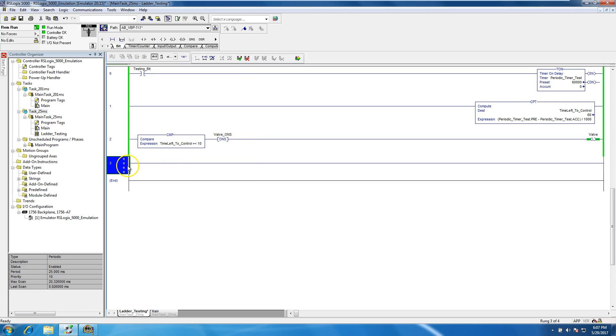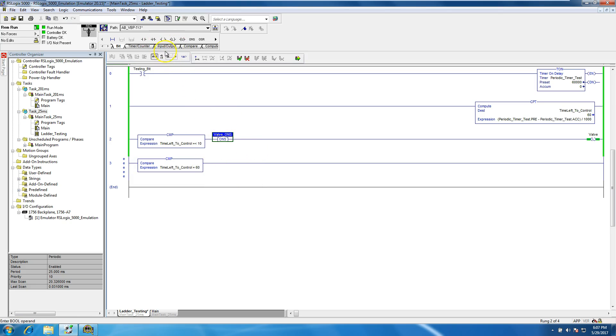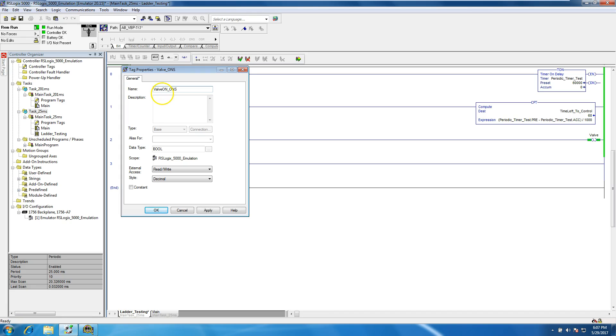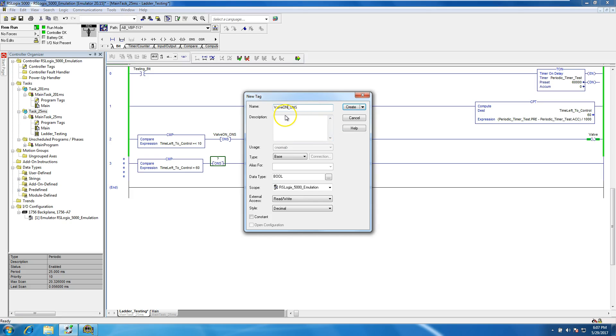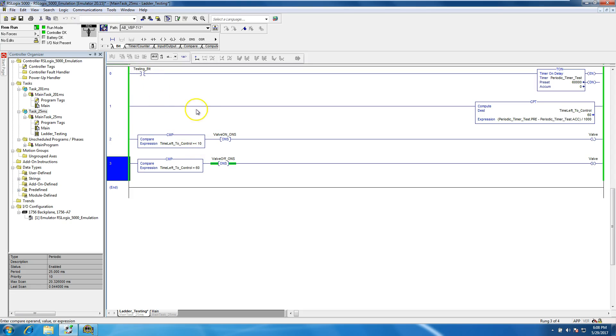The flip side is to copy and paste. We can say if equal to 60, then we want to come back and do an unlatch. We'll name the first one 'valve on' and the other one 'valve off'. We'll put another rung with a one-shot, paste it in, change it to indicate off, and then add a 'valve off' unlatch output.